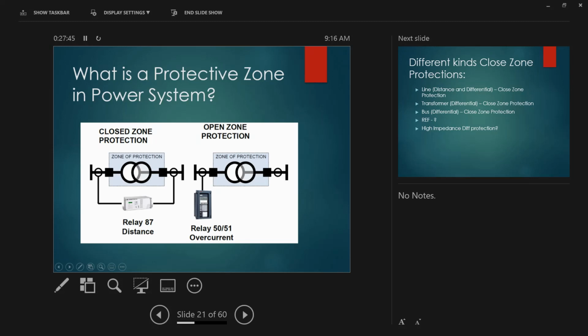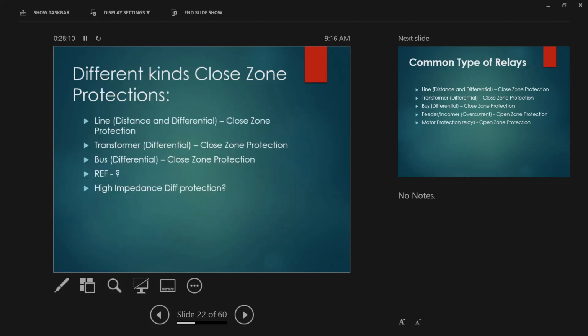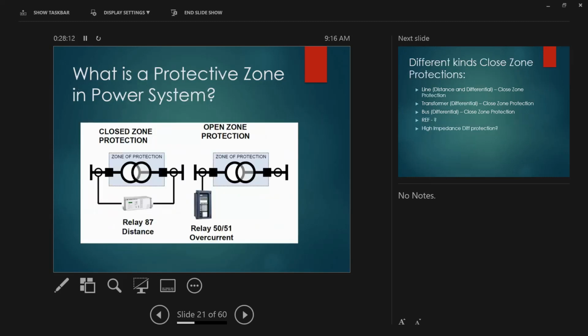When you say open zone protection, it means that 50/51 will cover the rest going downstream. It's not only specific to this one, but covers whatever fault downstream. If that one doesn't pick up downstream, this is the last line of defense that you have. So there are two kinds of protective zone. And those two kinds of protective zones can be on one relay? Can. Can. Can. So most of the relays now are multifunction.